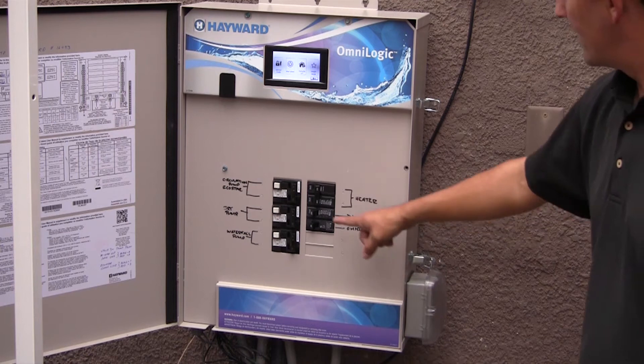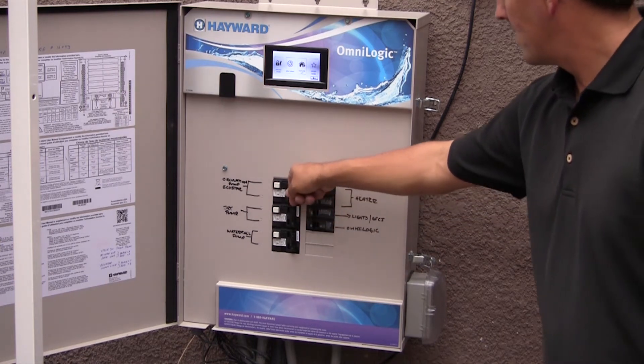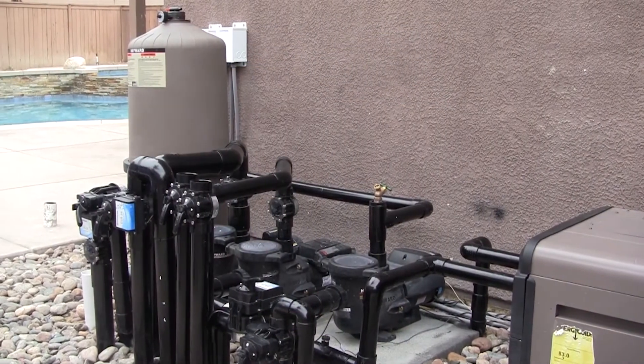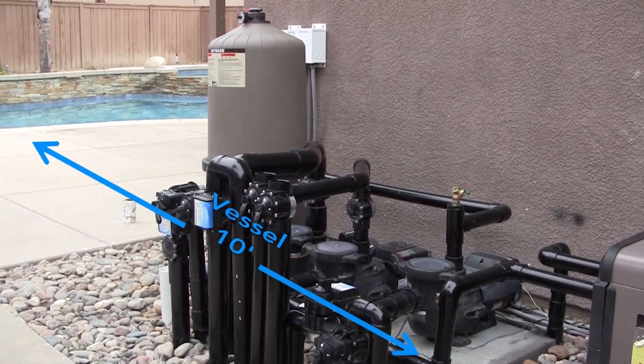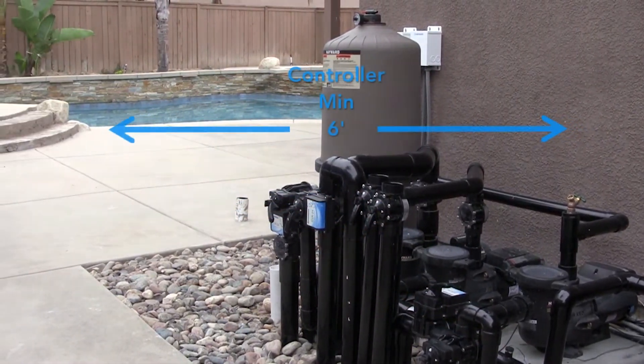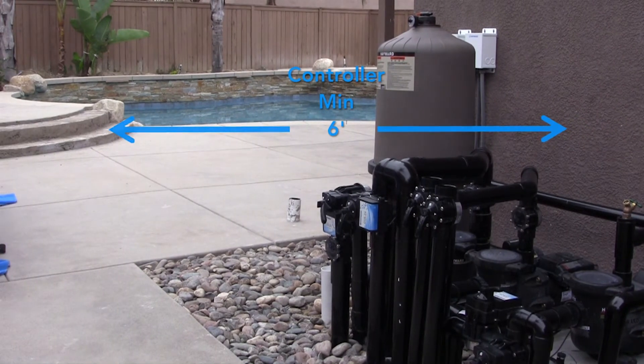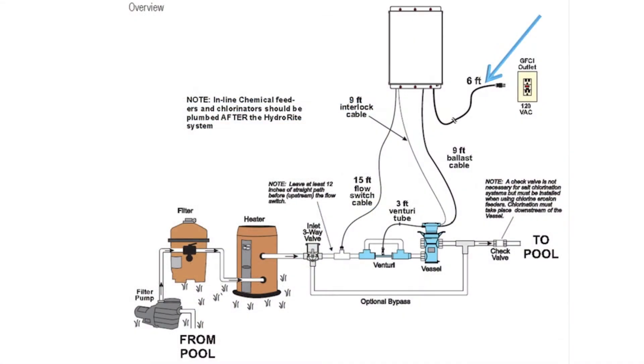Remove power to the pool filter pump before starting this installation. Installation must be performed in accordance with local and NEC code. The HydroRite vessel must be mounted at least 10 feet from the pool. The controller must be mounted a minimum of six feet horizontal distance — or more if local codes require — from the pool, and has a six-foot power cord that must be connected to a GFCI-protected circuit.